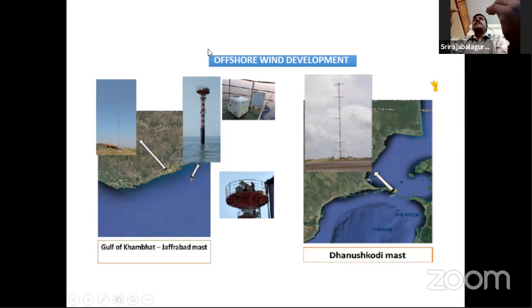That means even if you have a sudden dip or sudden fluctuations or flickers occurring, the grid should not separate out. We are talking about 1 megawatt or 2 megawatt, a small thing. But in a thermal power station, if a dip or any fluctuation occurs, they have to maintain the grid, so it should not separate out. That is a big capacity. For conventional power, a 210 megawatt or 600 megawatt unit is a different scenario. In a thermal power station, shift operators are always there, watching in the SCADA, so they can easily monitor and control it. But wind is a farm.